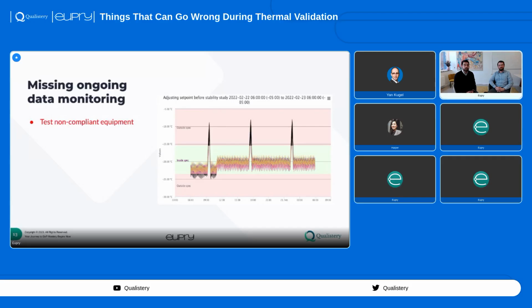So yeah, as the question in the poll says, if you do not have data monitoring while you do the mapping, it can result in testing non-compliant equipment. So that's a waste of money, that's a waste of time. And then afterwards you figure out actually that you can do some adjustments to make this unit compliant. But having the data monitoring, you will avoid doing that, and therefore you will not have this expansion of the timeline for the whole process. And I can see, Arslan, I'm just going to interrupt you really quickly. I can see that roughly 60% have experienced this exact thing that we talked about earlier as well. Yeah. Like really doing all your measurements and then basically finding out that the equipment did not pass. It's okay. That's a little more than I expected, at least, but it is something we see from time to time. Absolutely. Exactly.